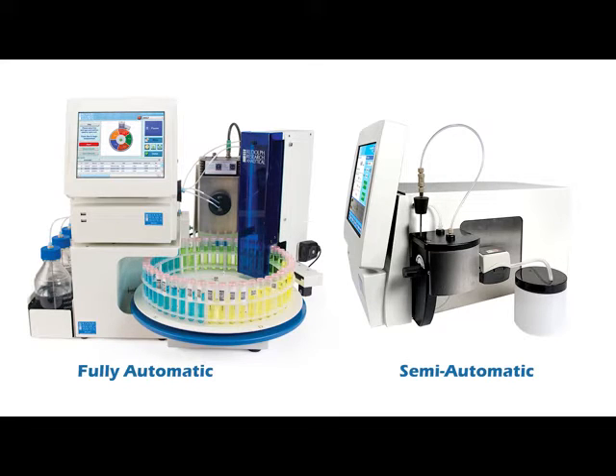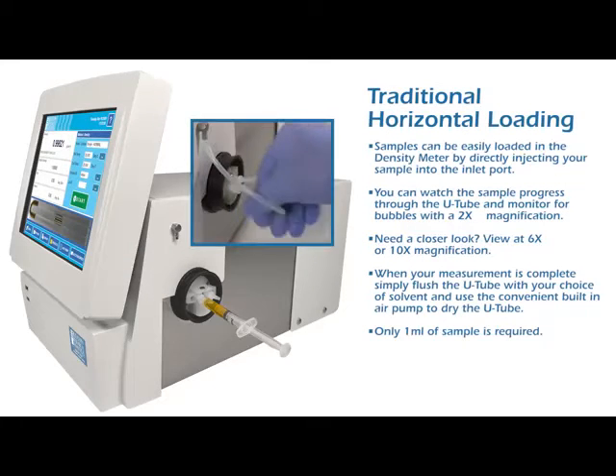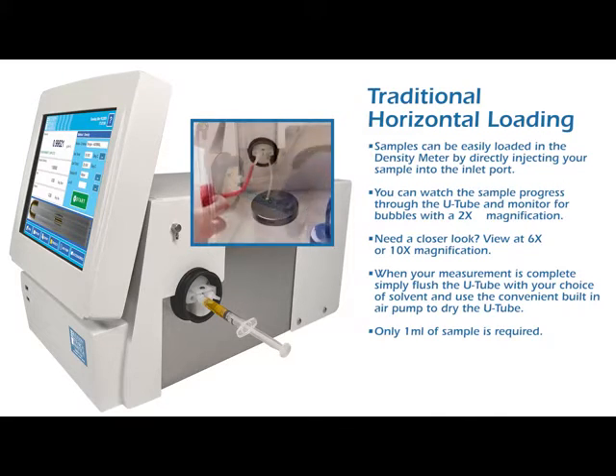Fully automatic and semi-automatic sample loading options are available. Traditional horizontal loading: samples can be easily loaded in the density meter by directly injecting your sample into the inlet port. When your measurement is complete, simply flush the U-tube with your choice of solvent and use the convenient built-in air pump to dry the U-tube. Only one milliliter of sample is required.